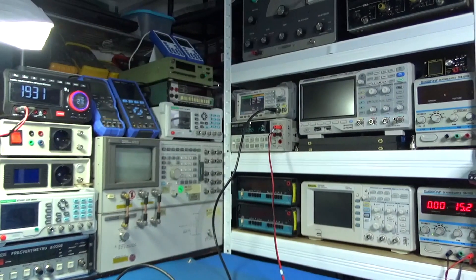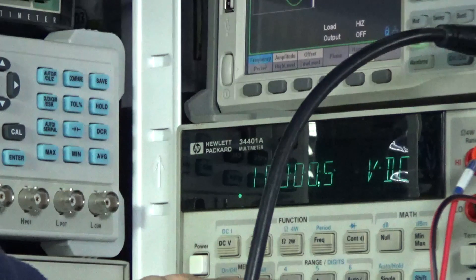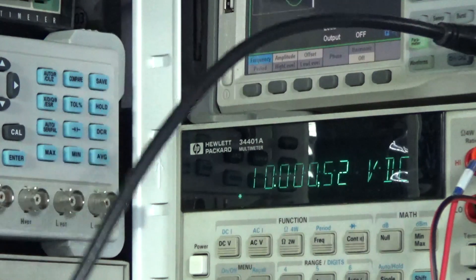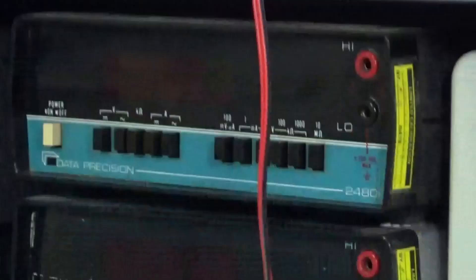I'm using a voltage reference of 10 volts and the multimeter says 10.01 volts. It's on the specs. We can compare with a six-and-a-half digit multimeter with higher precision — our Venlab is on the specs.